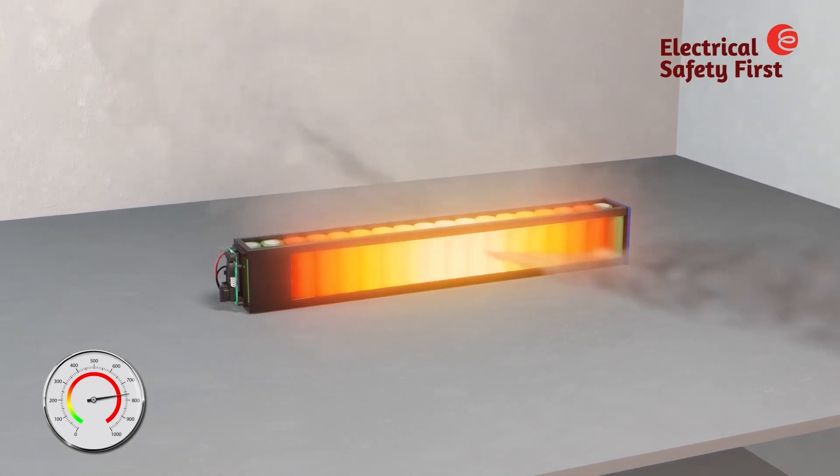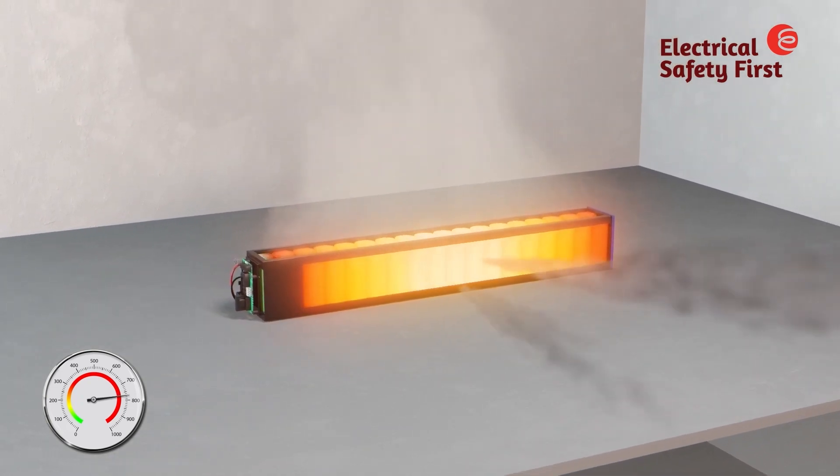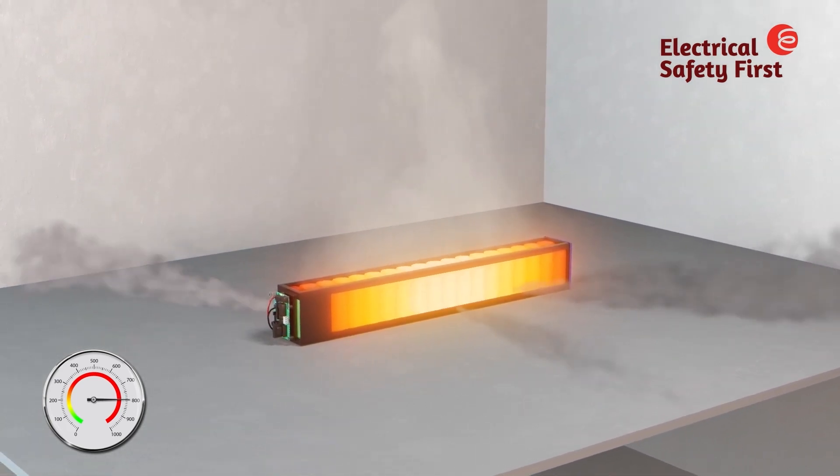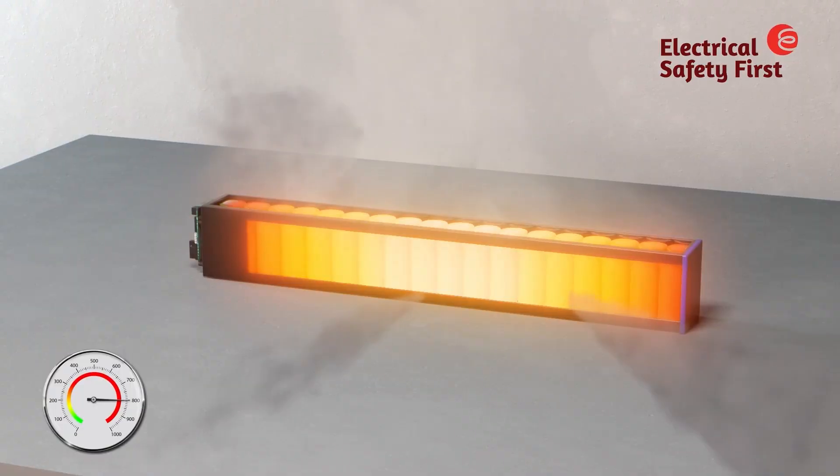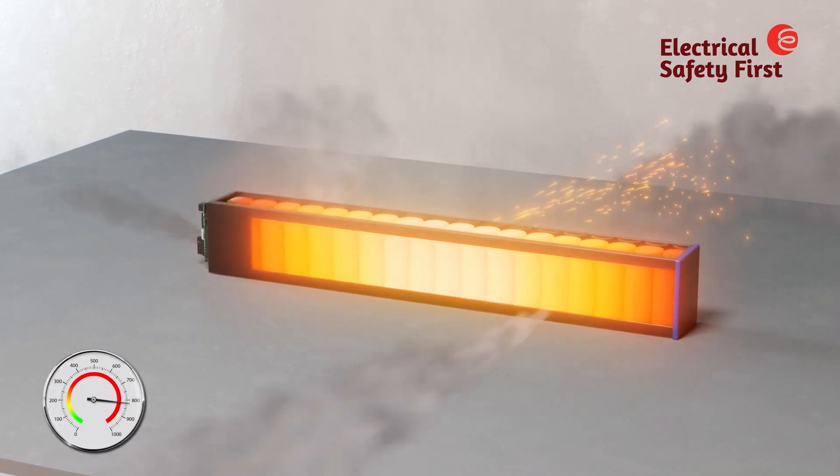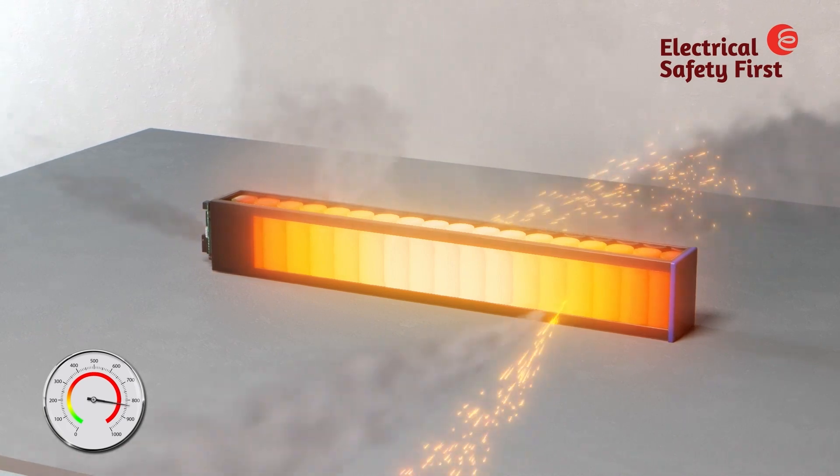Once this exothermic reaction gets hold, even removing external sources that may have caused it will not prevent thermal runaway and a battery fire or explosion. The temperature of the cell accelerates uncontrollably and can reach temperatures in excess of 700 degrees Celsius.